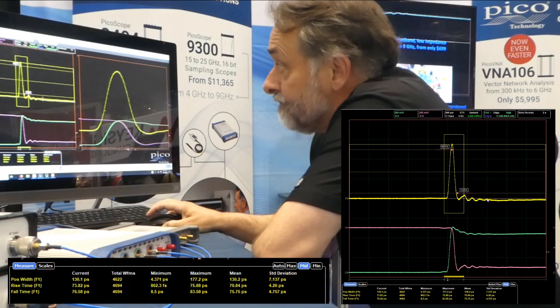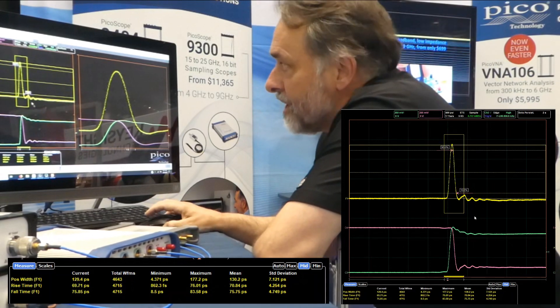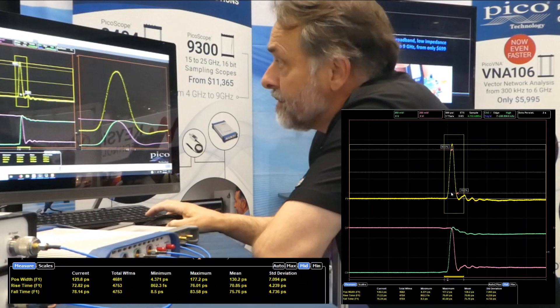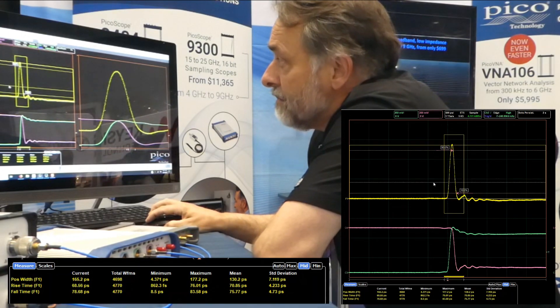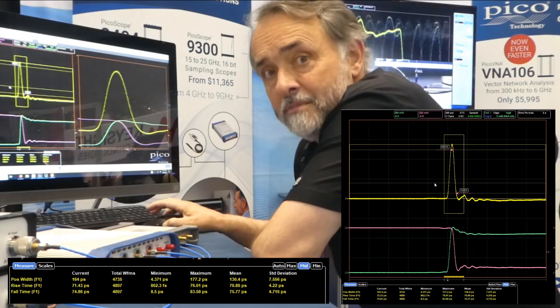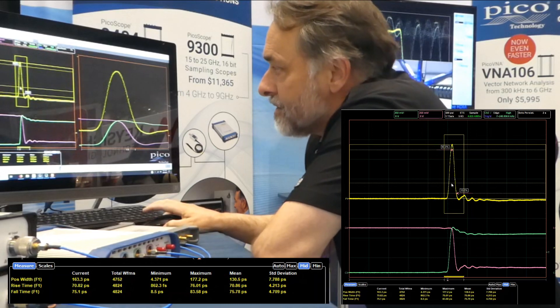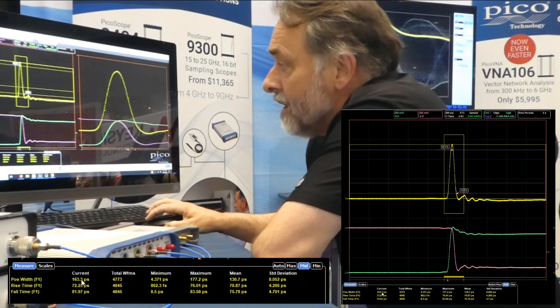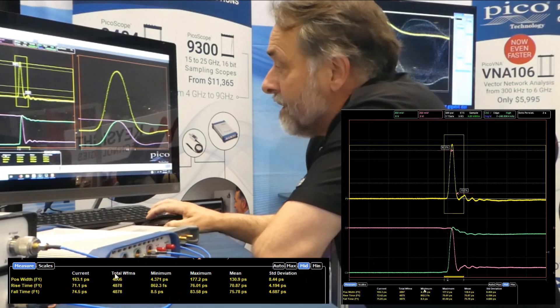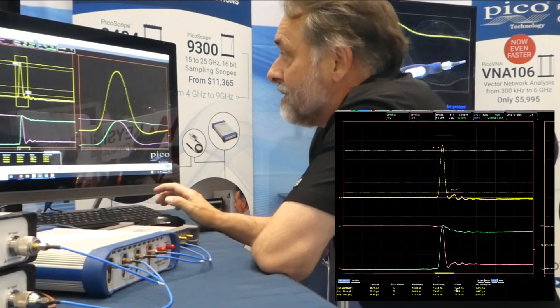The software conveniently displays all mesials associated with that measurement: the top, the base, and the 90, 50, and 10 percent mesials. I can control those mesials — I can simply grab them and pull them up and down. In the scientific world we quite often see pulses measured at the 30 percent mesial, and you can see I can do that — it can be set accurately in the menu. Now we have a pulse width of about 162 picoseconds being displayed here as the mean.